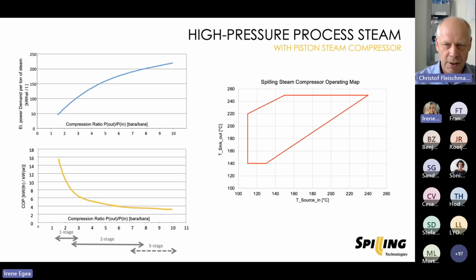diagram, or we call it a temperature operating map, you see which temperatures can be reached with up to a 3-stage compressor as a function of the temperature on the source side. There you see that up to 250 degrees Celsius are possible when we have on the source side, say, about 150 degrees Celsius, meaning about 5 bar inlet pressure. Then we can even come up to 35-40 bar on the outlet side, which corresponds to the 250 degrees Celsius.